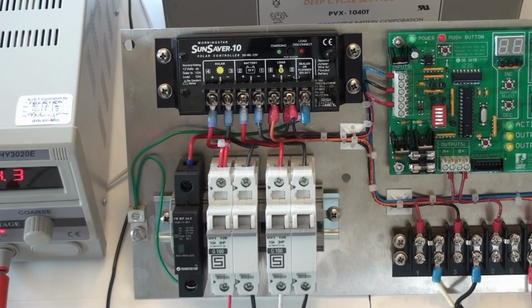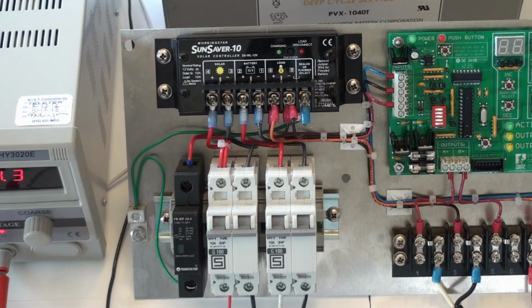If the green status LED indicating battery charge is not on the charge control unit, begin tracing the problem by first measuring the voltage at the input terminals of the charge control unit. They should measure between 14.5 and about 22 volts, depending on the panel. If the voltage is not measured at the input terminals, trace it back to the circuit breaker that feeds the voltage to the charge control unit. First with the output, then on the input.